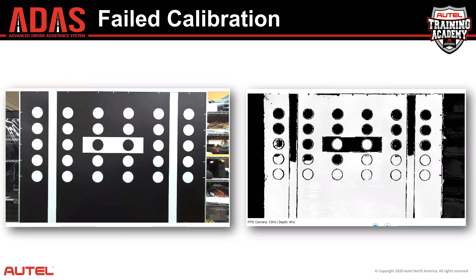Now, when you look at them side by side, it's easy to see that there's some glare on the target. But I will tell you that 99 out of 100 calibration techs would not see this target, if this is all they had to look at, as being improperly lit. It looks pretty darn good, but it's not until the calibration fails. This can cause technicians a lot of hassle trying to get a calibration to pass, to the point that they start second guessing themselves and redoing their measurement and adjusting the target position and the target height, trying to get things to pass. And really, it's just a matter of adjusting shop lighting just a little bit.